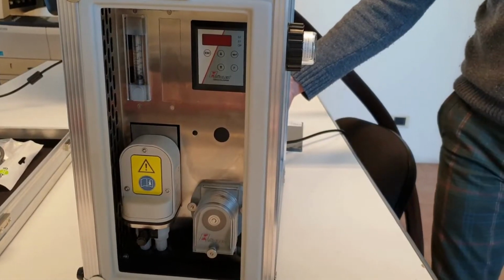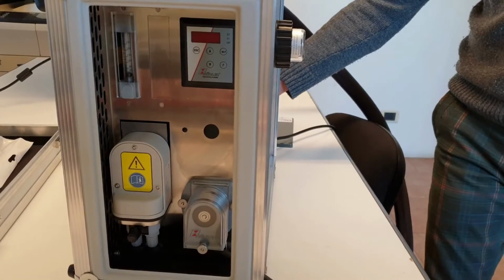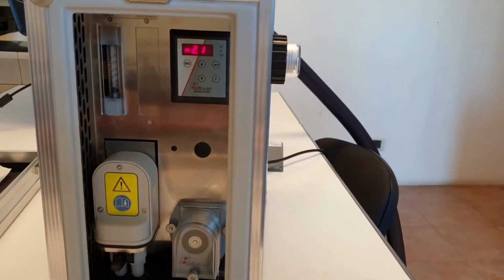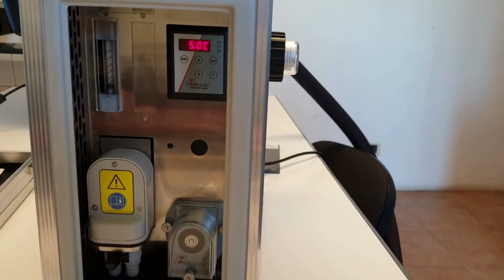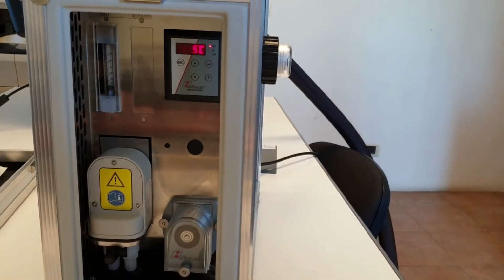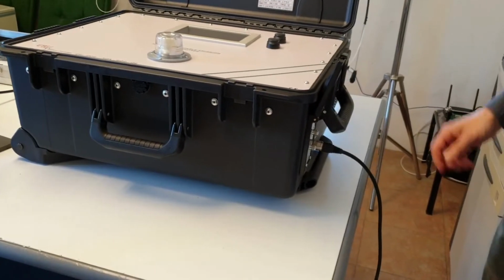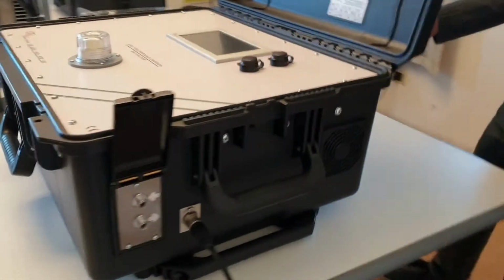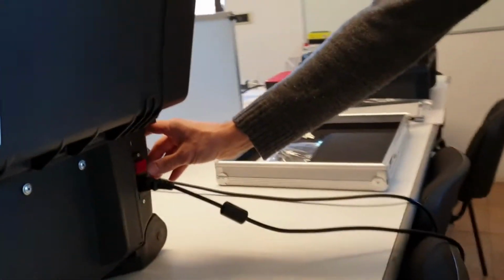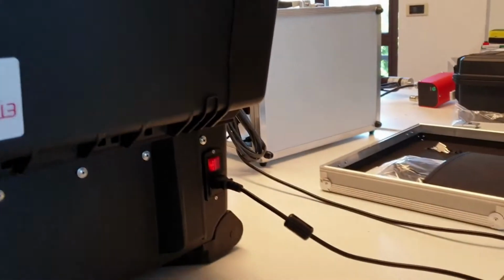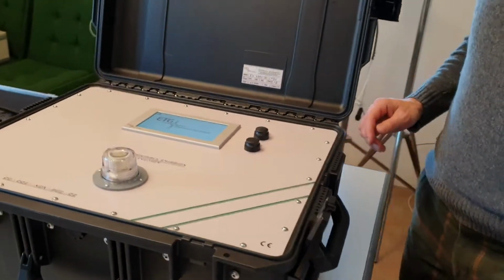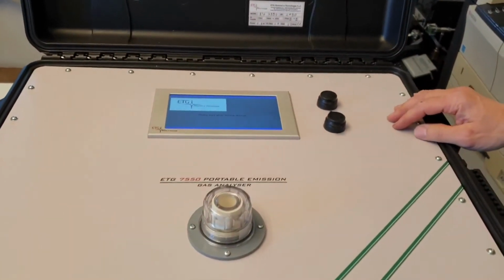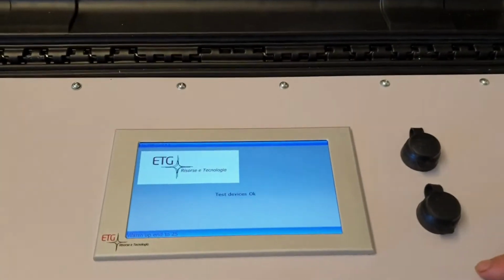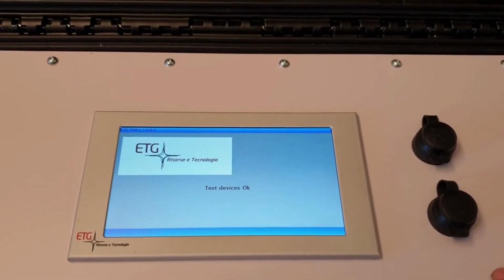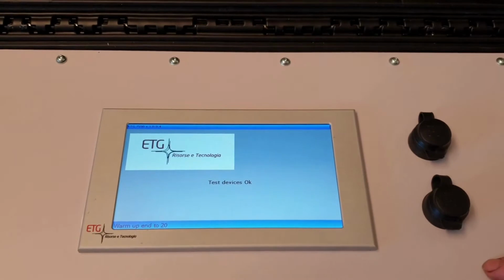You can switch on the sample conditioning unit. Now we can switch on the analyzer. The switch is on the back. The analyzer does a beginning test and starts with the automatic cleaning done with the internal pump.